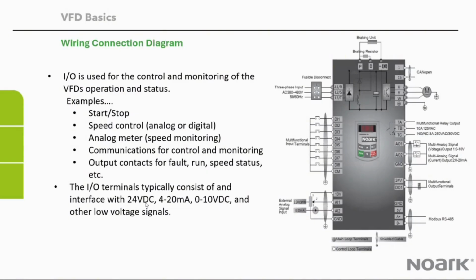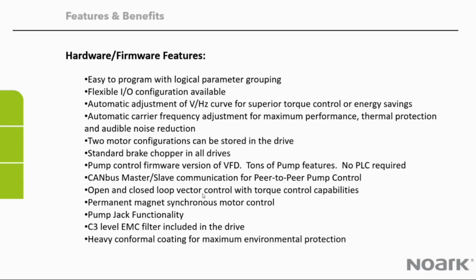And we talked about it before. The I/O terminals typically are 24 volt DC level. In my previous lives, I've seen 115 volt control. More globally, it's all gone to 24 volts DC. We have a 4 to 20 milliamp output or an input. We have a 0 to 10 volt DC for the same scenario.